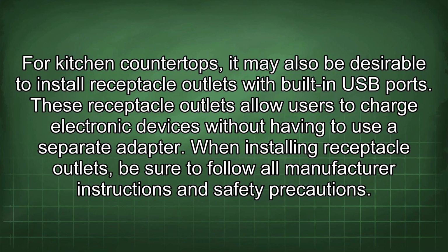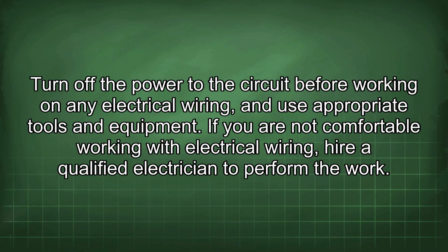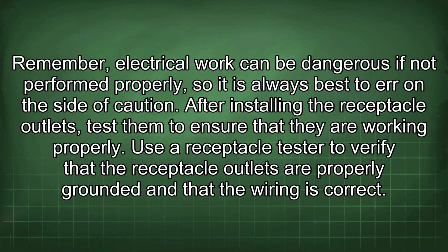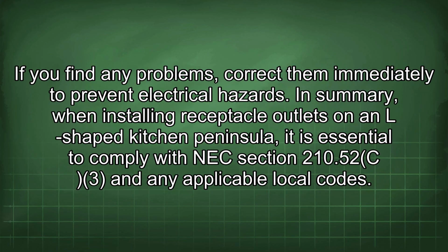When installing receptacle outlets, be sure to follow all manufacturer instructions and safety precautions. Turn off the power to the circuit before working on any electrical wiring, and use appropriate tools and equipment. If you are not comfortable working with electrical wiring, hire a qualified electrician to perform the work. Remember, electrical work can be dangerous if not performed properly, so it is always best to err on the side of caution. After installing the receptacle outlets, test them to ensure that they are working properly. Use a receptacle tester to verify that the receptacle outlets are properly grounded and that the wiring is correct. If you find any problems, correct them immediately to prevent electrical hazards.